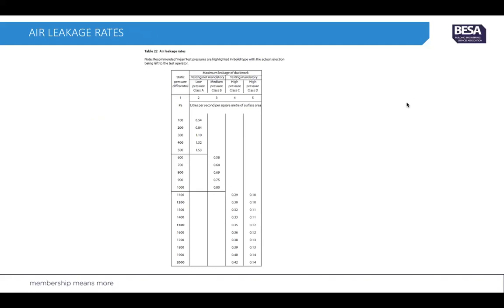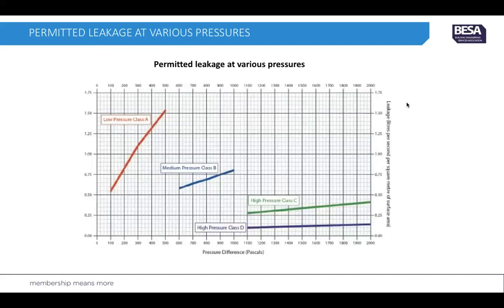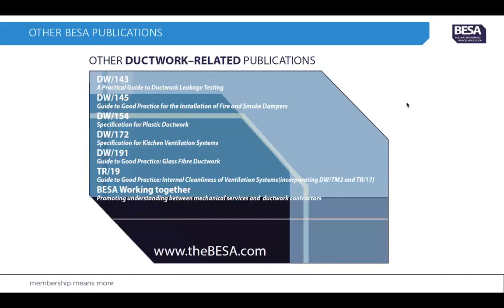At the back of DW143 there are air leakage rate tables. For example, at 500 pascals Class A the maximum is 1.53 litres per second per metre squared of surface area. For the test chosen earlier — 1500 pascals Class C — it is 0.35 litres per second per square metre of surface area. These figures are also presented in graph form showing the differences between high and low pressure classifications, illustrating that Class D high pressure requires a very well-constructed, well-sealed ductwork system.